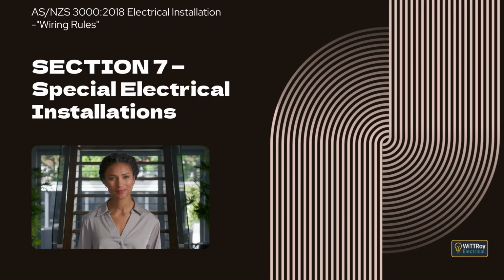Clause 7.2.10.1 General. This clause explains that motor room less lifts do not require a traditional lift motor room due to their design. It explains that an MRL switchboard must comply with Clause 2.10, and that MRL lifts fitted for emergency evacuation, firefighting activities, or designated as emergency lifts must meet the additional requirements of this clause.